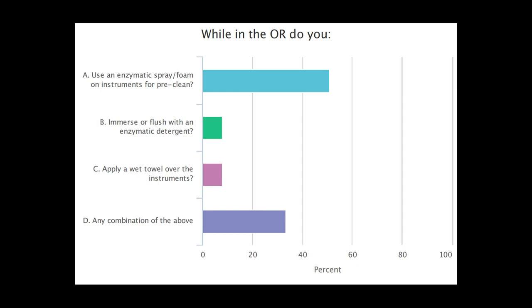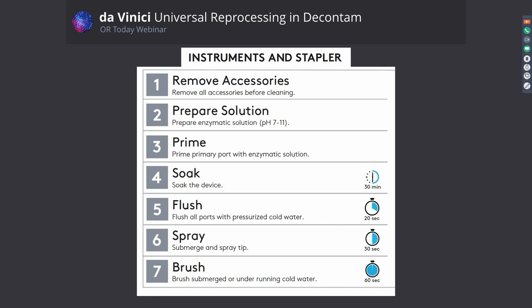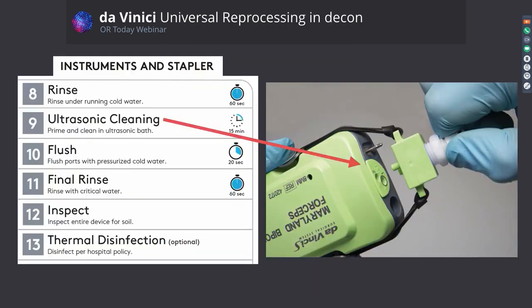So the instruments come down, we're talking about the robotic instruments. They leave the OR and come down to sterile processing, and you remove any accessories that may still be on these instruments or have not been taken off, for example. And you prepare an enzymatic solution and you prime your instruments. You'll actually inject detergent solution into your robotic instruments through adapters, through tubing, and you soak the devices for 30 minutes. You flush them for 20 seconds, and you spray them, you brush them, you try to turn the dials and make the different articulations with the device so that you can clean all the surfaces that aren't necessarily exposed. You rinse for 60 seconds and then ultrasonic cleaning.